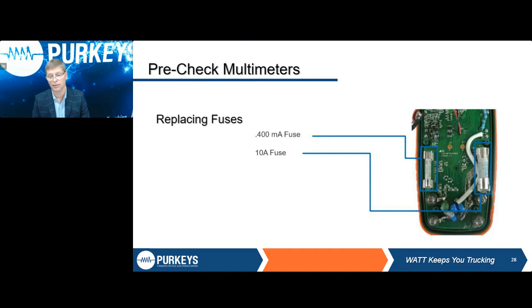Talking about that fuse too, these are special fuses. No matter how much you use your meter, at some point you're going to do something foolish and hook up your meter in the wrong setting. You're going to blow that fuse. It did exactly what it's supposed to. It protected your meter. If you see in the slide right now, the one on the right is the 10 amp, the one on the left is the 400 milliamp. These are special fuses, what's referred to as a fast acting slow blow fuse. What that means is they'll handle that 10 amps all day long, but if you exceed it by very much at all, they are designed to blow quickly to protect your meter. So if you do blow one, sorry about your luck. You're going to go spend $15 to buy a new one, but spend the money, replace it, make sure you're good to go. Do not ever replace this with a Wrigley's wrapper, a 22 shell, or a fuse out of your old pickup truck. You have to use the right type.